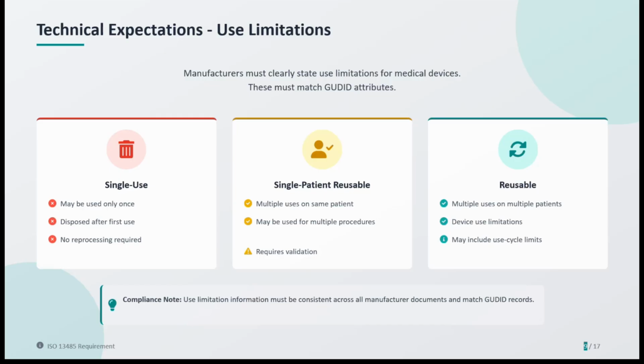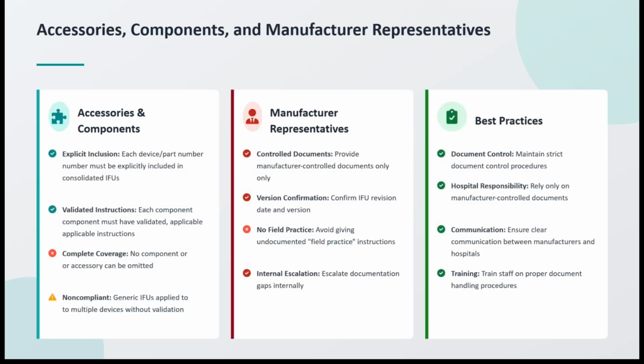Now, there are specific requirements and best practices for accessories, components, and the role of manufacturer representatives. Every device part number and every accessory must be explicitly covered and identified in the IFU. For our clients, we do associate generic IFUs when appropriate, but we do not assume they are valid across all reference numbers. We work directly with the manufacturer to confirm that the generic instructions truly apply to all of the listed devices, and that any additional assembly or disassembly documents are clearly referenced within the document.